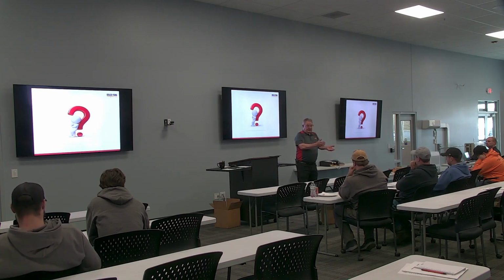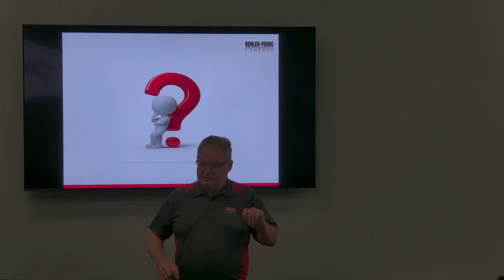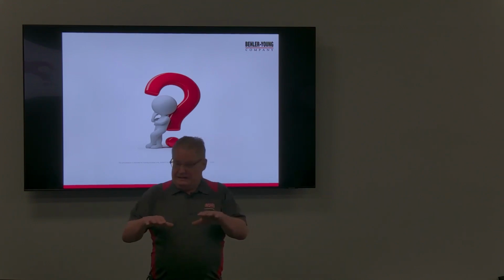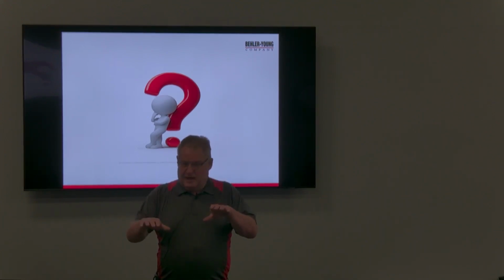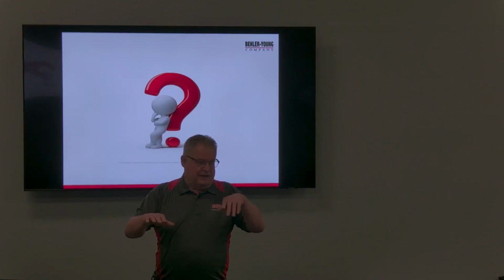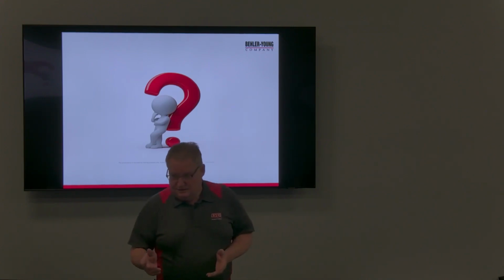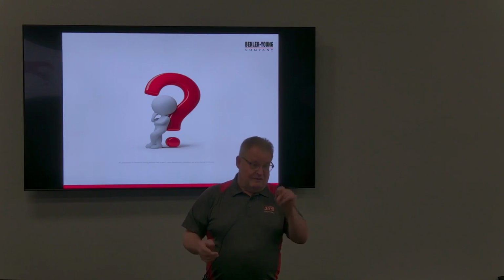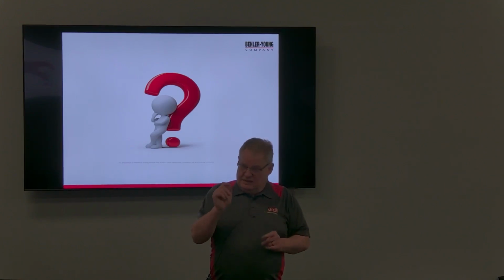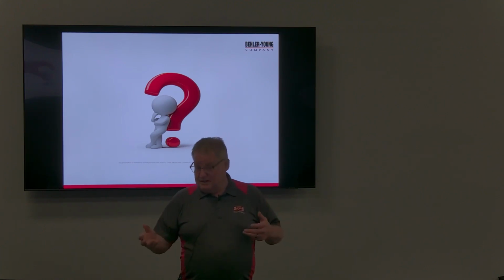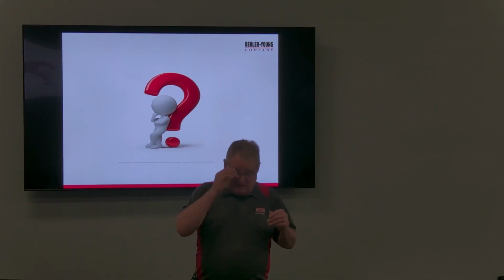So a perfect example, R410A is 50% R32, 50% R125, right? Pretty easy, 50-50 mix. So if I had a leak and I lost more of the R125, I'm no longer 50-50, now I'm 52-48. I recharge it again, 54-46. Okay, that's called fractionization. So when I'm losing more of one than the other. Now, R410A, the difference is really, really tiny. So with 410 they determined we can recharge 5, 6, 7 times without any problem of fractionization.